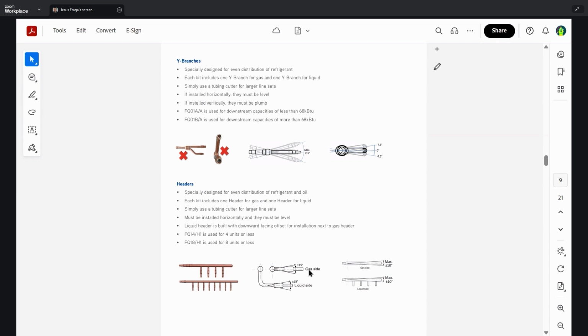The liquid header is built with a downward facing offset for installation next to the gas header, as we illustrated here in this picture. So this is the L shape of the liquid line, and the gas will sit on top of it if you choose to install it that way. As long as they're horizontal, you don't have to necessarily do this, but they are designed to fit right on top of one another.